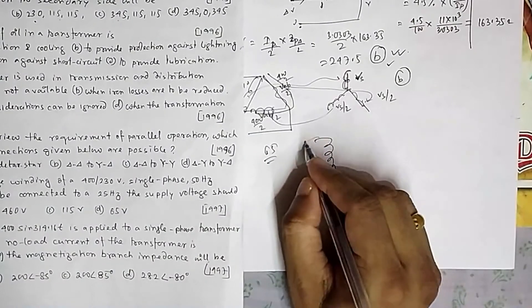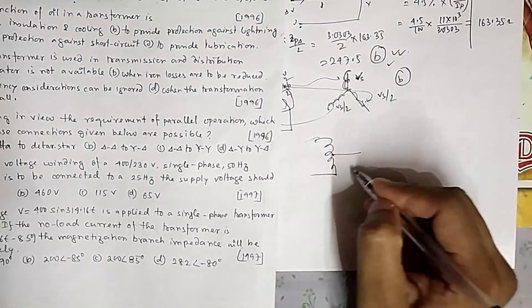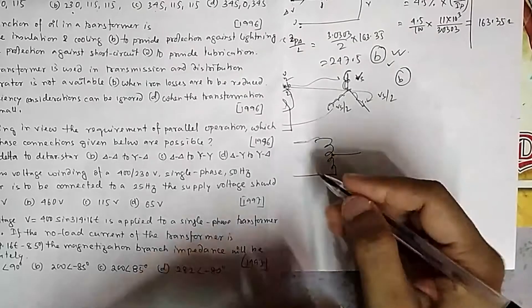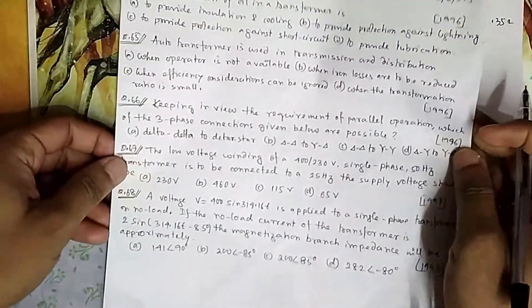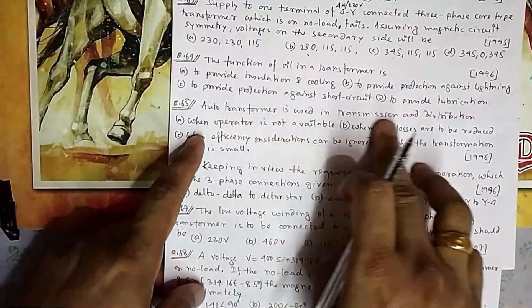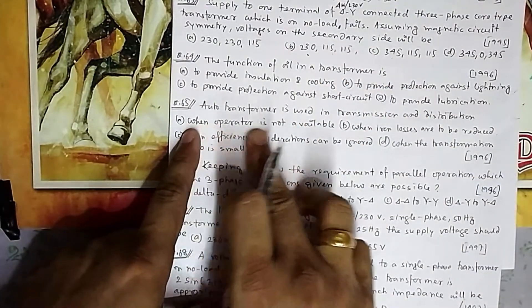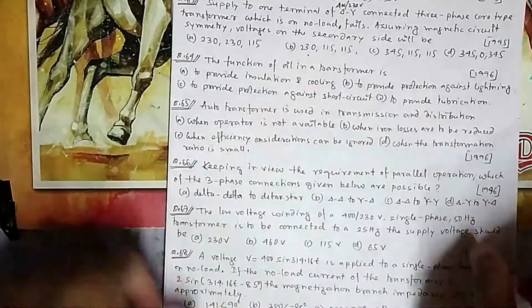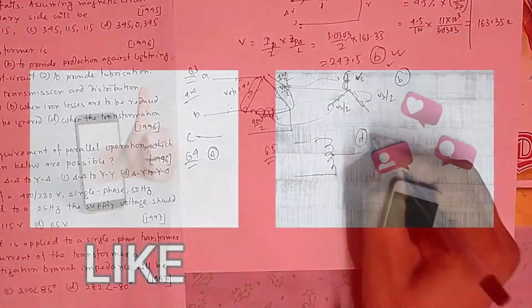Question 65: An auto-transformer is a single-winding transformer — you supply across one portion and take output from another. Because only one winding is used instead of two, you save copper. However, the disadvantage is that it cannot be used for large transformation ratios. It is suitable for small ratios like 1:1.2, 1:1.5, but not 1:2, 1:4, or 1:5. The 'auto' does not mean automatic; the reason for its use is a small transformation ratio to save copper — that is option D.